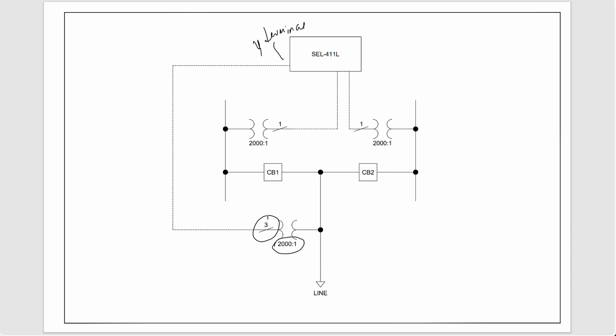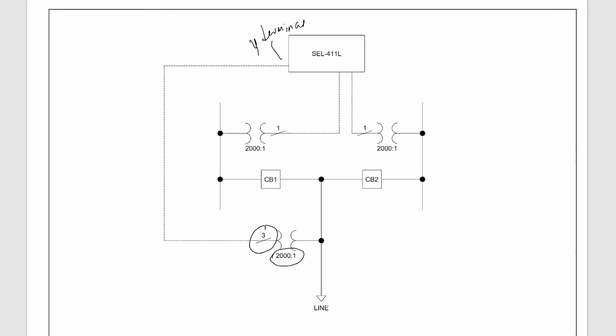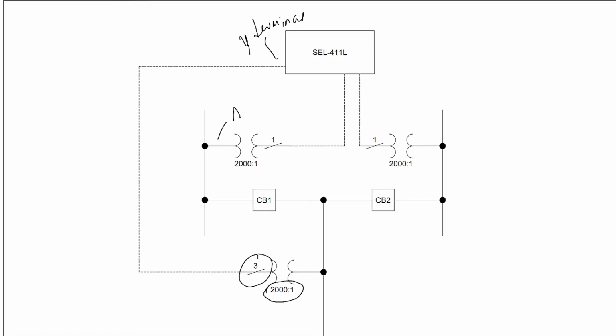In this case, the relay is implemented, again, in a double bus, double breaker configuration, so we can set it up to check for synchronism across both CB1 and CB2, so the two breakers that we have over here. So in other words, we can implement two sync check elements, one for each breaker. Now we'll assume that the bus 1 single phase PT connection is wired to the A phase on that bus. So this PT would be wired to the A phase, and that's going to be fed to the VAZ input on the relay.